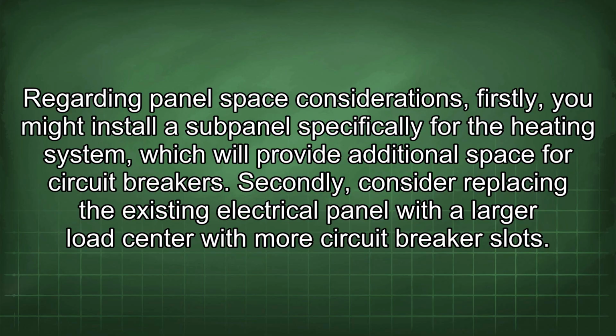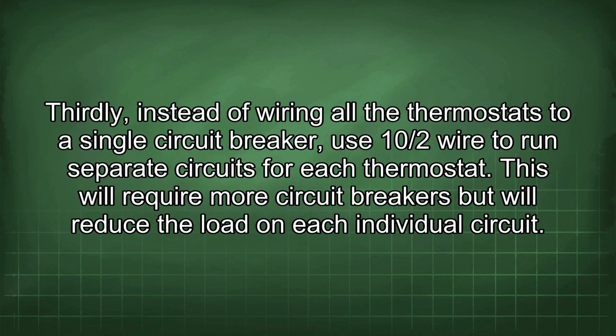Regarding panel space considerations, firstly, you might install a subpanel specifically for the heating system, which will provide additional space for circuit breakers. Secondly, consider replacing the existing electrical panel with a larger load center with more circuit breaker slots. Thirdly, instead of wiring all the thermostats to a single circuit breaker, use 10/2 wire to run separate circuits for each thermostat. This will require more circuit breakers but will reduce the load on each individual circuit.